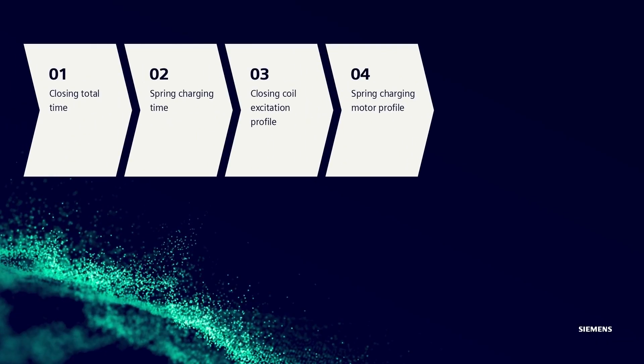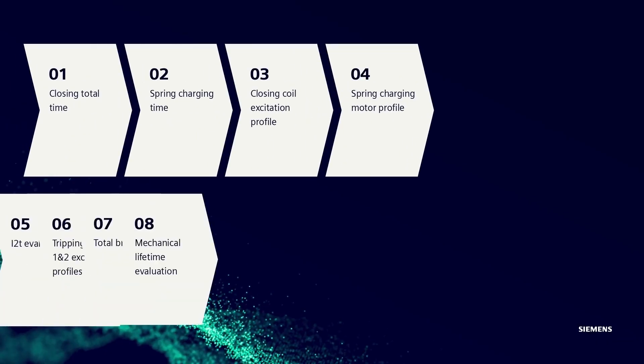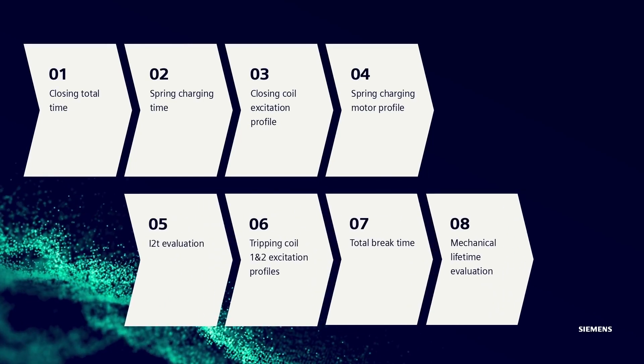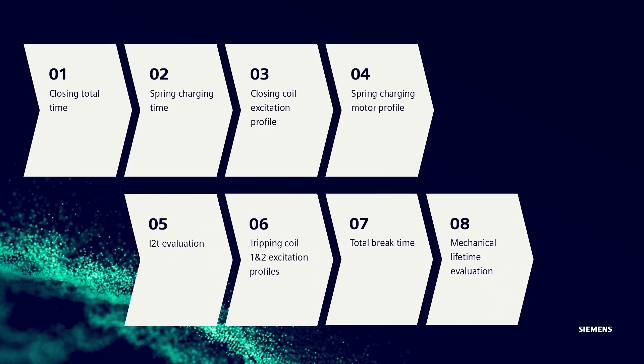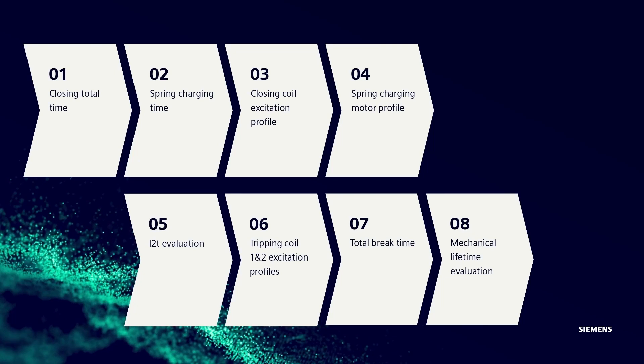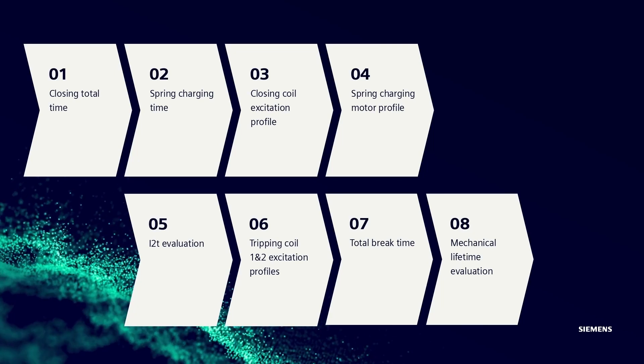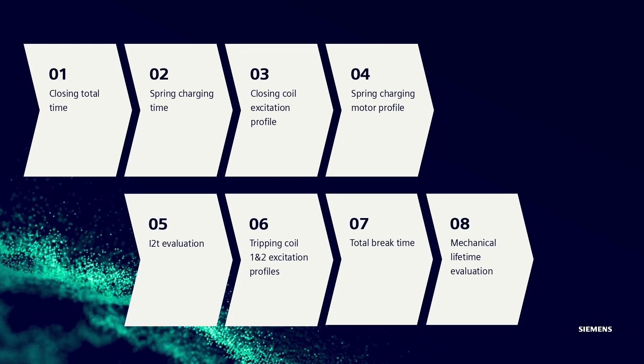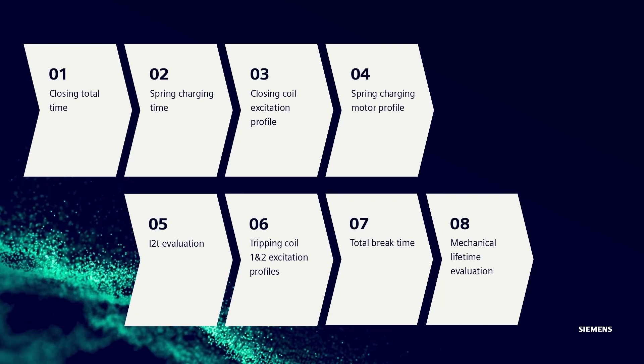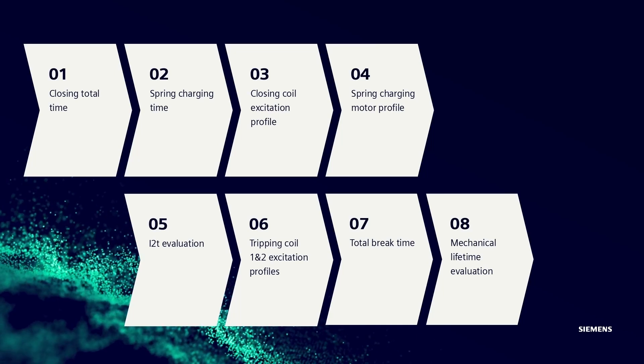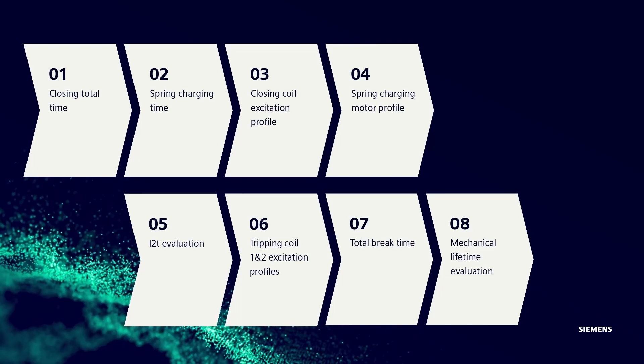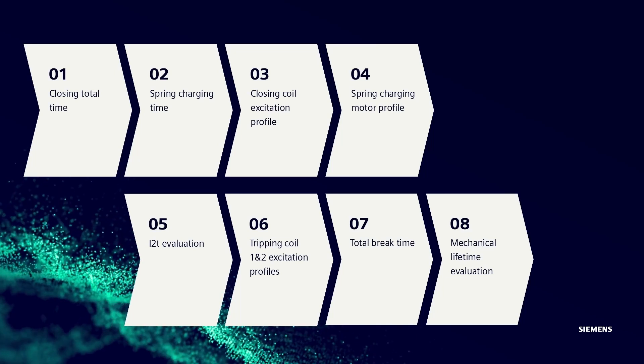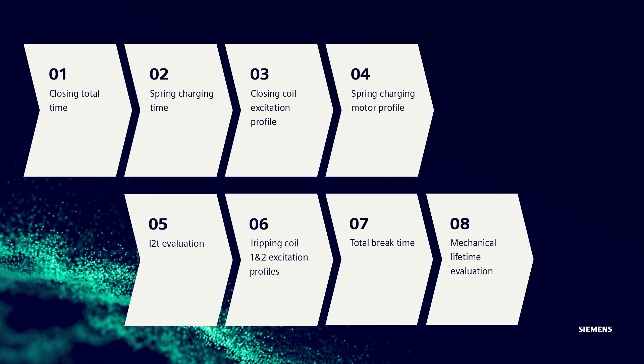Analysis includes data such as Closing Total Time, Spring Charging Time, Closing Coil Excitation Profile, Spring Charging Motor Profile, I2T Evaluation, Tripping Coil 1 and 2 Excitation Profiles, Total Break Time, and Mechanical Lifetime Evaluation.